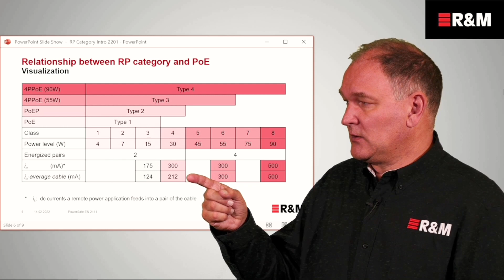This table here actually shows the interrelationship between the PoE types and the RP categories. We have on the top here the different types showing the different classes of PoE which represent the different power levels that you can transmit in PoE. What we see in here, for example, for a type 2, a PoE plus, is that the individual current per wire is 300 milliamps, which equals to 600 milliamps per pair. So we have 300 milliamps, but we are only using 2 pairs out of 4 in a cable. So if we're averaging out the current to all pairs, we would end up with 212, which is exactly the value that RP1 is giving you.